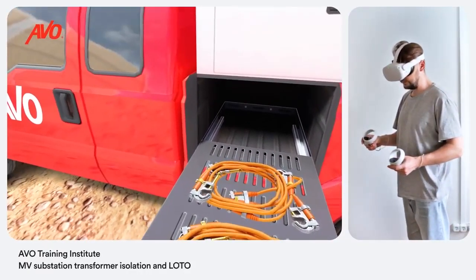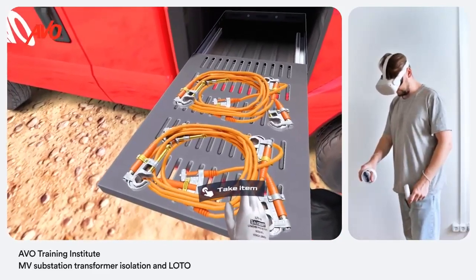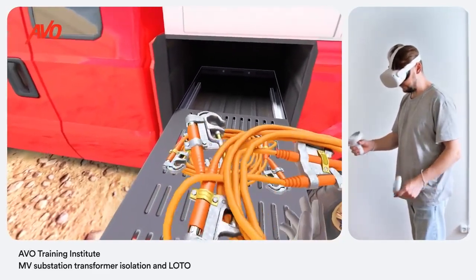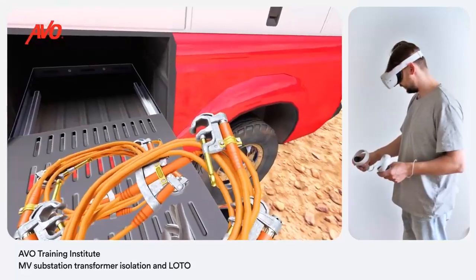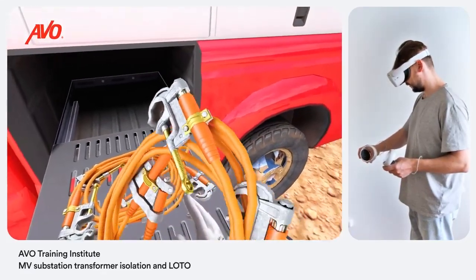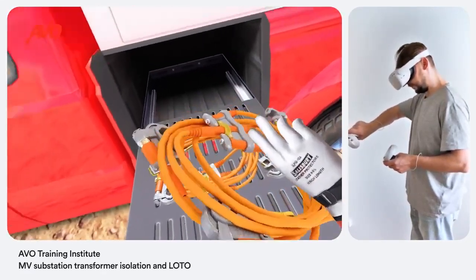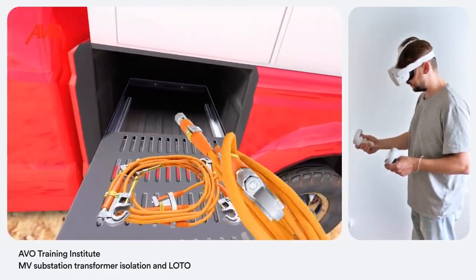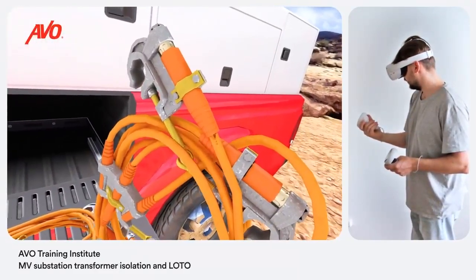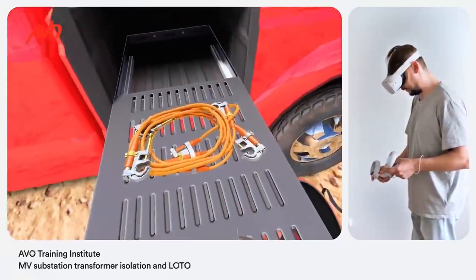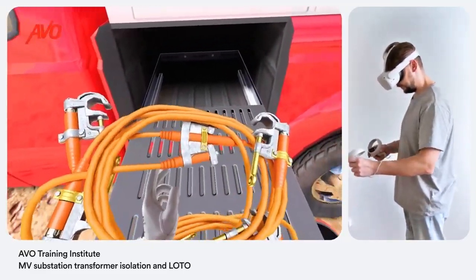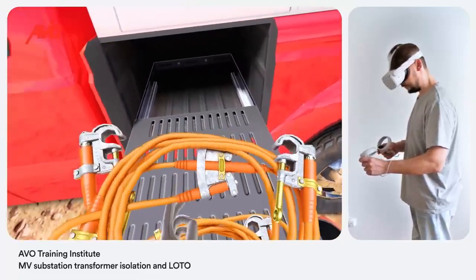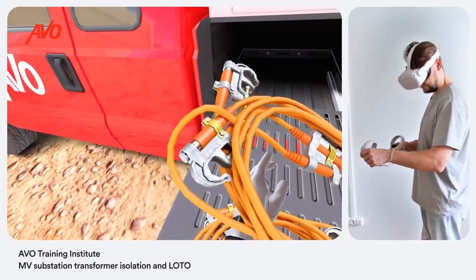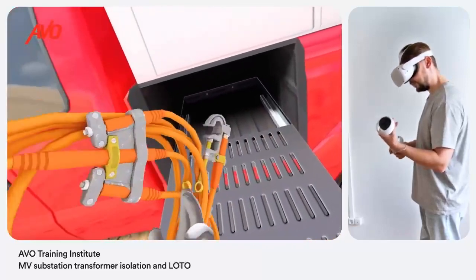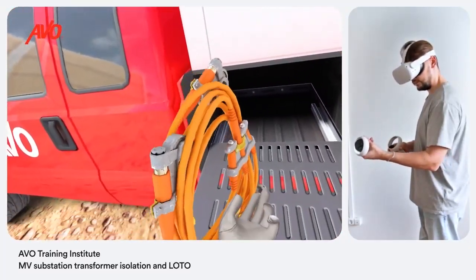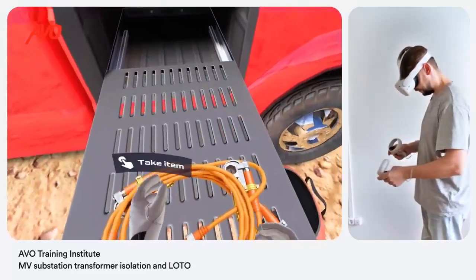Personal protective grounds shall be visually and manually inspected for cracked or broken ferrules and clamps, exposed broken strands, cut, mashed, kinked or flattened cable, jacket damage, cracks or damage to clamps and ferrules. Check clamps for smooth operation through the entire range. Check torque of pin-type terminals and jam nuts on threaded ferrules. Look for dirt, grease, oil, oxidation on current-carrying surfaces, and any other obvious conditions that would adversely affect performance. If any of these conditions are found, the PPGs shall be rejected. Put the PPGs into a tool bag.